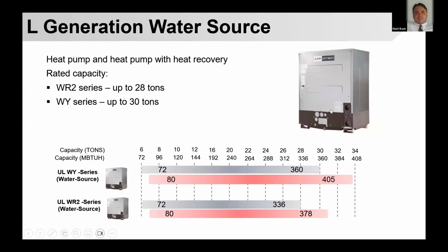These modules are meant to interface with variable refrigerant flow, refrigerant-based systems. So the modules exchange heat, absorbing or rejecting it to a refrigerant loop that sends it to individual refrigerant-based fan coils, but their heat sink is on the water side.